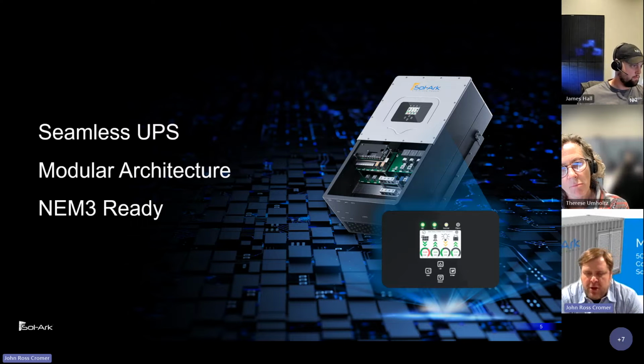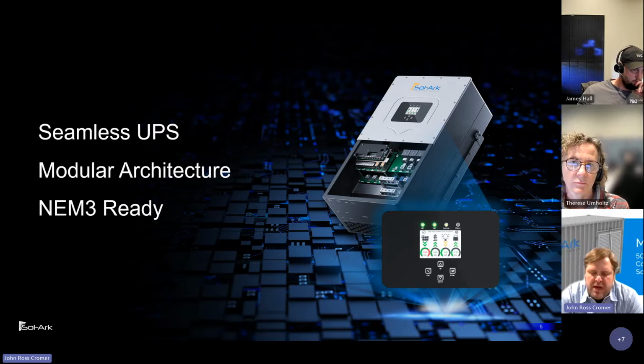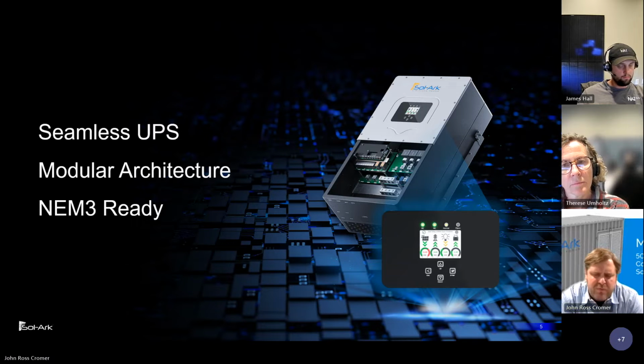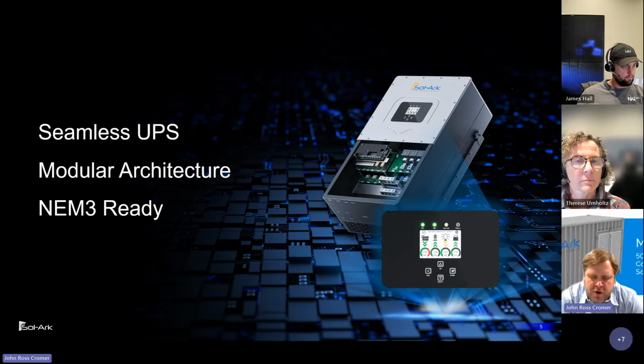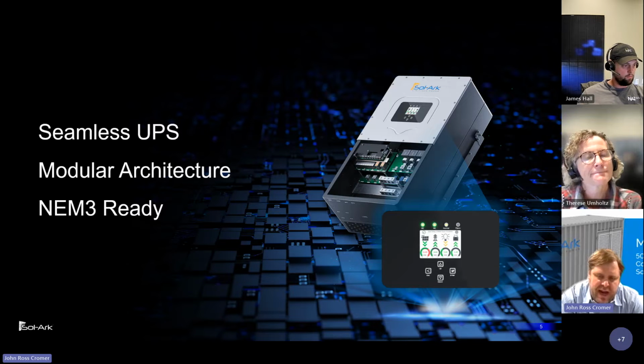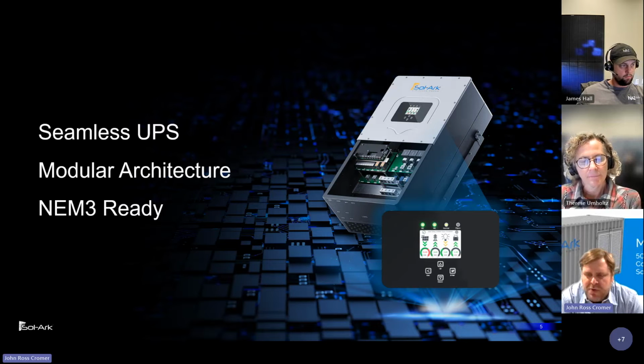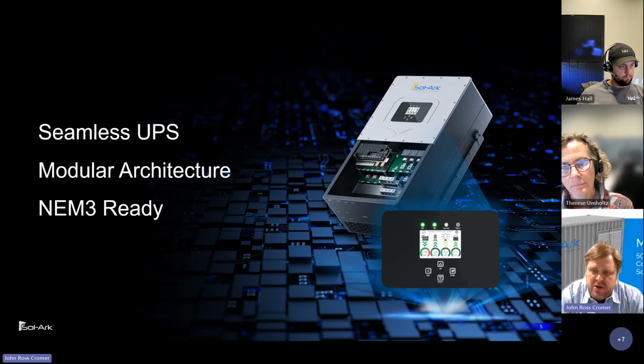Throw in that generator port, that multi-purpose port, and you can effectively roll out Sol-ark onto every job site, even though every job site is a little bit different. Every job site has a unique interconnection strategy. The Sol-ark platform is so versatile that it can cover a lot more bases than our competitors. Let's say you had a 1200 amp panel board and you wanted to do a full 1200 amp grid pass-through. Well, each inverter has 200 amps of grid pass-through. You just do 6 inverters through a supply-side connection, and you could pass through a 1200 amp panel board and back it up with 300 amps of service. Or you could add 6 more inverters and get another 300 amps of backup.